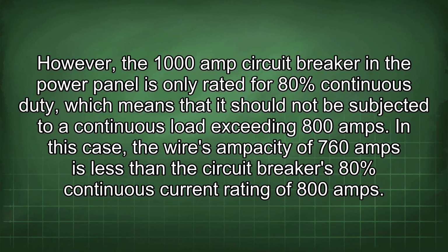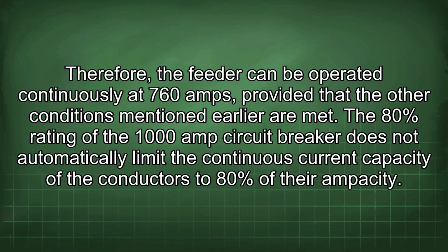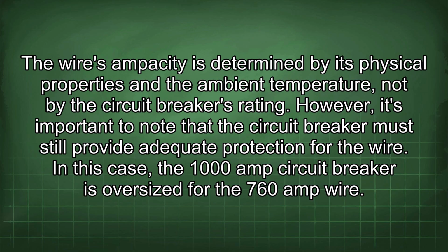In this case, the wire's ampacity of 760 amps is less than the circuit breaker's 80% continuous current rating of 800 amps. Therefore, the feeder can be operated continuously at 760 amps, provided that the other conditions mentioned earlier are met. The 80% rating of the 1000 amp circuit breaker does not automatically limit the continuous current capacity of the conductors to 80% of their ampacity. The wire's ampacity is determined by its physical properties and the ambient temperature, not by the circuit breaker's rating.